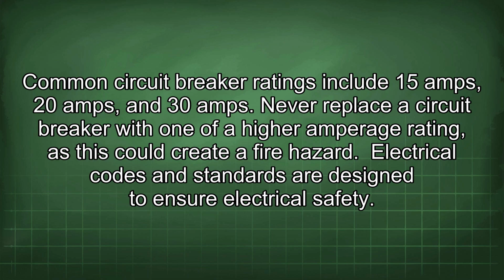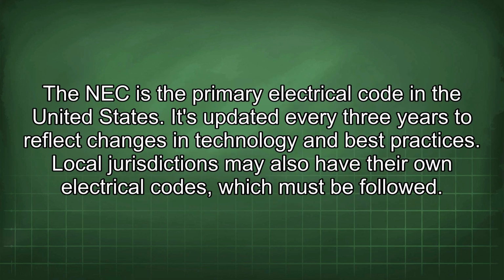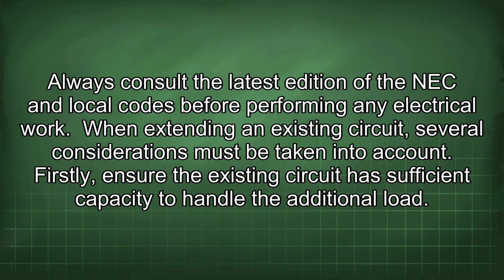Never replace a circuit breaker with one of a higher amperage rating, as this could create a fire hazard. Electrical codes and standards are designed to ensure electrical safety. The NEC is the primary electrical code in the United States. It's updated every 3 years to reflect changes in technology and best practices. Local jurisdictions may also have their own electrical codes, which must be followed. Always consult the latest edition of the NEC and local codes before performing any electrical work.